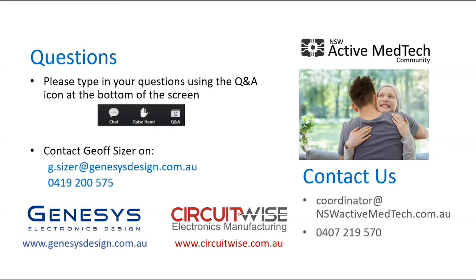In the former case, you don't need to have necessarily demonstrated the veracity of the device before you do that trial. You can do it, but not rely on those outputs rather than information gathering. However, if you want that information to stand up as an input to your final clinical submission, you need to make sure the device you use has been developed under design control so that you can link the results back to what was the condition of the device you actually used. So it can get quite complicated.